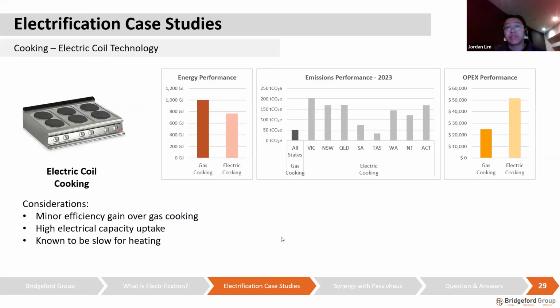And so with electric coil technology, as you can see here, the performance is quite similar if we compare it with electric space heaters and electric domestic hot water systems. The efficiency gain is not that great. It's only a 20% increase, and the emissions outcome is actually quite terrible. OPEX is also really high, and it's also known to be really slow for heating, so nobody likes this technology. Typically, we won't recommend this technology at all.